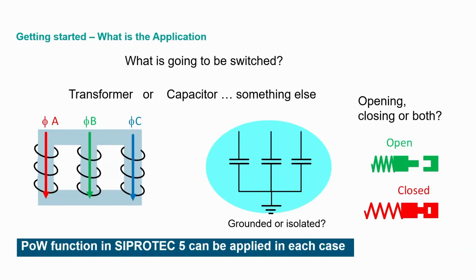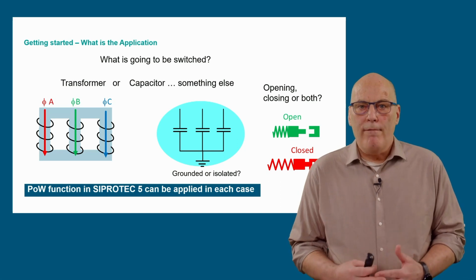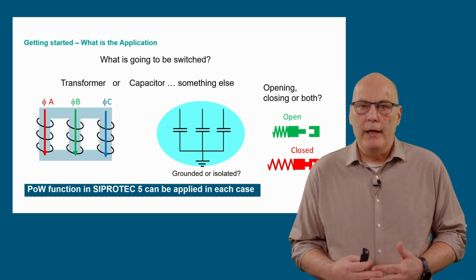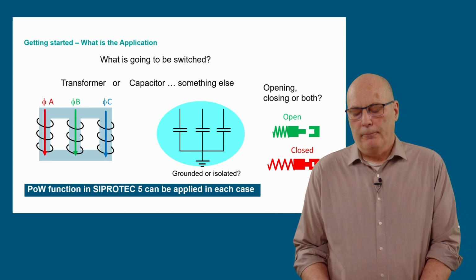To get started, you need to note your application: transformer, capacitor, or something else. Is the capacitor grounded or with isolated start point? Then you must decide if the application will be for closing, opening, or for both. The point-on-wave function in SIPROTEC 5 is prepared for all of these applications.